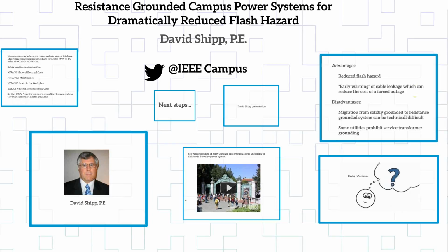One of the last things I did 2 years before I retired was spend 2 weeks with Boeing out in Everett, Washington, where they lost power at 13 kV and melted the whole substation down, lost two 115 MVA transformers. It cost them probably $9 or $10 million in their facility, and the 15 kV switches were literally melted down. 80% of the metal and stuff is just a puddle of metal at the bottom.